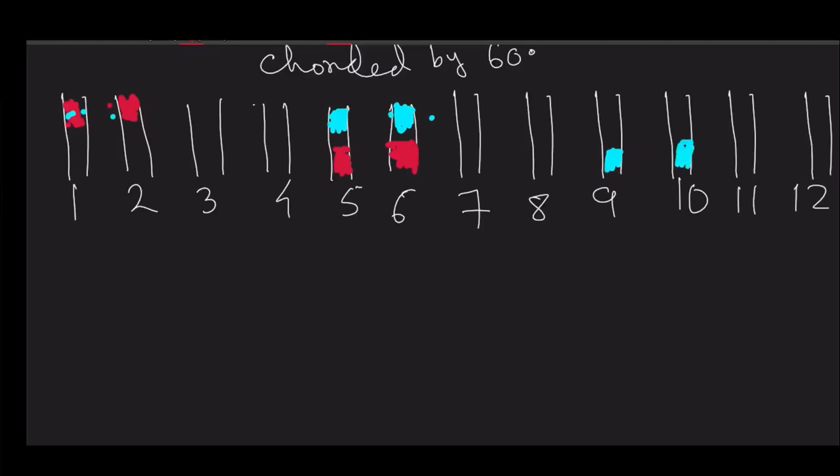Well, now what about C? I have mentioned that C should also be placed just 120 degree apart from this. If B starts at 5, then the upper layer of C should occupy this. However, for the lower layer it should be 9 plus 4 that is 13.